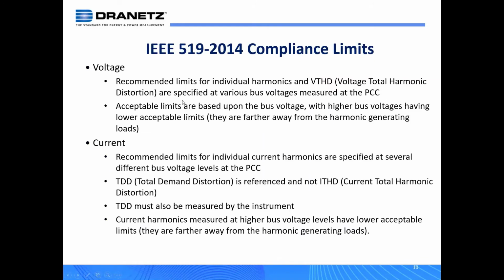So there are compliance limits for voltage and there are compliance limits for current. For voltage, the recommended limits for individual harmonics and VTHD, which is voltage total harmonic distortion, are specified at the various bus levels measured at the point of common coupling. So the acceptable limits are based upon the bus voltage, with higher bus voltages having lower acceptable limits. And really the meaning behind this, the rationale, is that what produces harmonics are the loads that we have in the system.